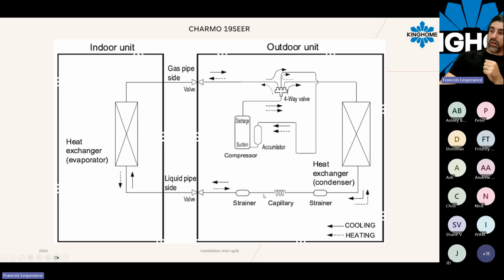So we have a liquid state, low pressure here right after the capillary tube. Again, we hit another strainer to protect the systems both ways. And then we will send out the amount of liquid refrigerant to the evaporator.